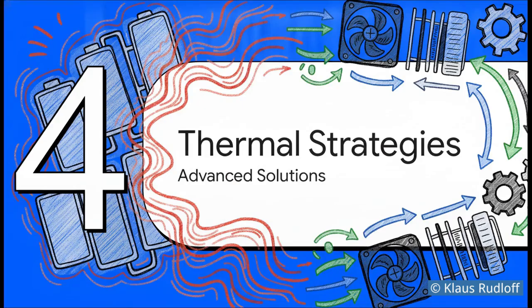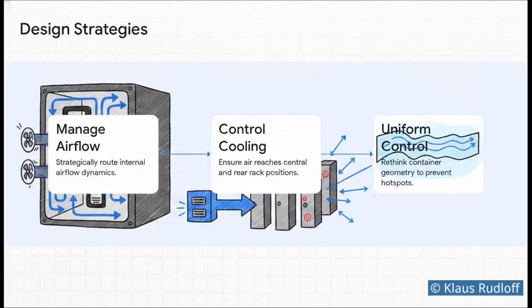Let's pivot to Section 4, Advanced Thermal Design Strategies. We can't just point out the problem; we have to look at advanced solutions to engineer our way out of it. First, we've got to intensely manage internal airflow dynamics. We can't just blow cold air into a box and hope for the best; we have to strategically route it. Next, we must actively control cooling distribution, ensuring air actually reaches those problematic central and rear rack positions. Finally, we need to deploy advanced, proactive strategies for uniform temperature control across these high-density racks. This might mean fundamentally rethinking the internal geometry of the containers themselves to prevent those core hotspots from ever forming.